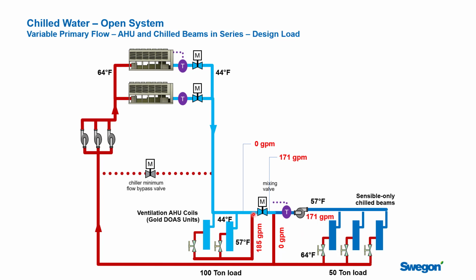At this point in the pipe, you have 185 GPM. You only need 171 GPM of that 57 degree water right here. So what should happen is you would take 171 GPM of that flow and send it out through here. You don't have to mix anything from anywhere else. Run it through your chill beams and send it back. And so there'd be zero flow through this return line here. Your problem is you've got 185 GPM in this pipe, and this valve is going to pinch down and only let 171 GPM through here.